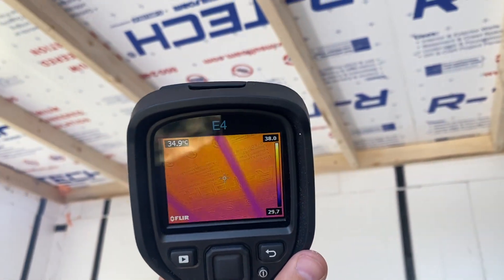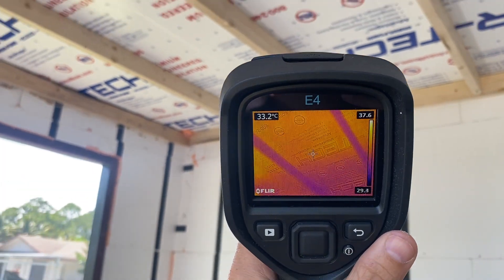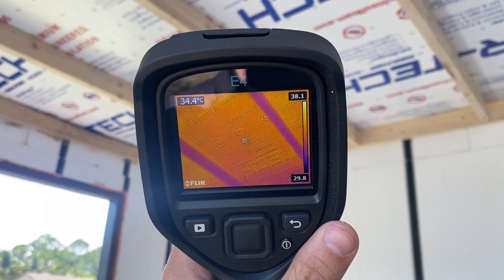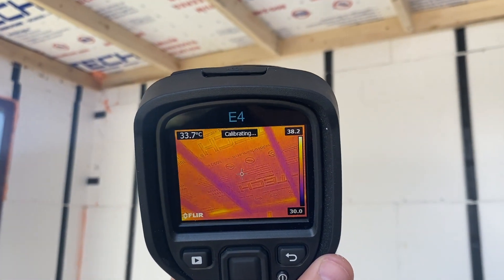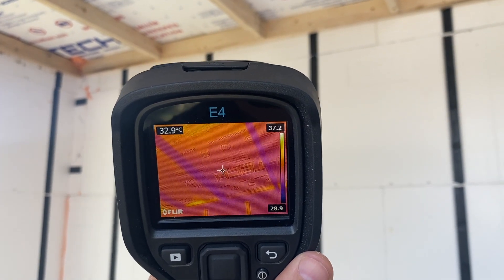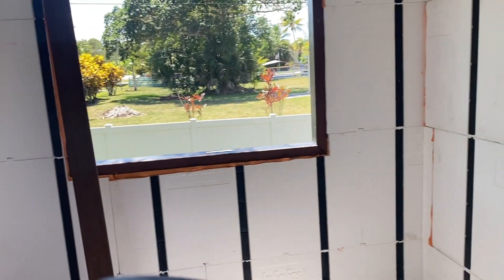Up here on the roof, we've got a painted area where you can kind of see it's purple. That's painted white right now. That's where I stopped painting it. We jump up to about — right now it's kind of shaded — about 35. Here we go down to about 32 and a half to 33 degrees. So, two degrees Celsius change there.